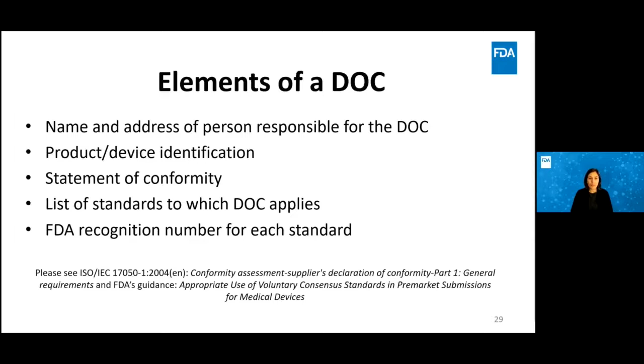The appropriate use guidance stipulates the following elements for a DOC: the sponsor's contact information, the device's identifying information, the actual statement of conformity, and all of the standards being cited, and you must be sure to include the FDA recognition number for each standard. Other elements are included in the next slide. So those other components of the Declaration of Conformity are the date and place where the declaration was issued, the signature of the responsible party, and any limitations on the validity of the declaration, and finally, any supplemental documentation supporting the Declaration of Conformity.